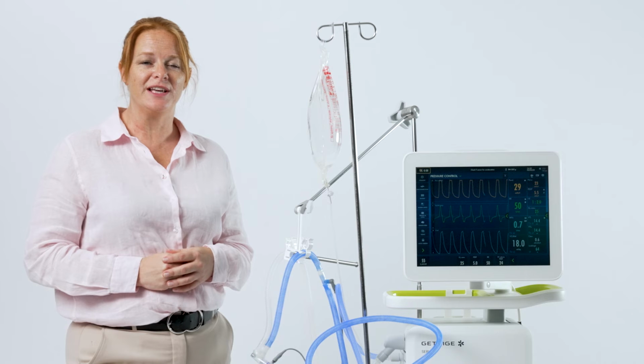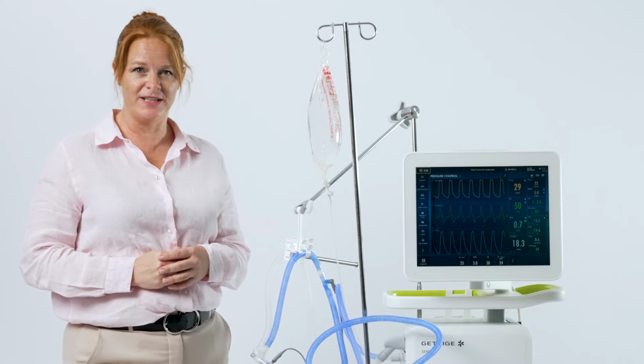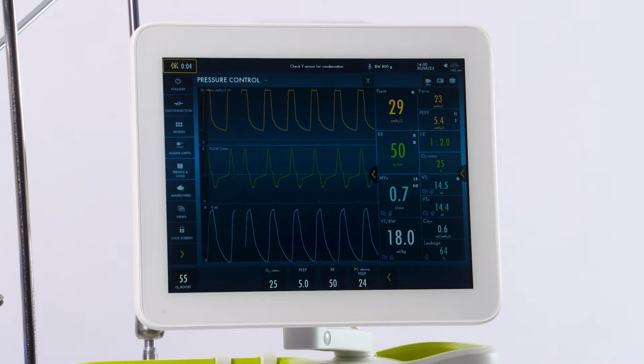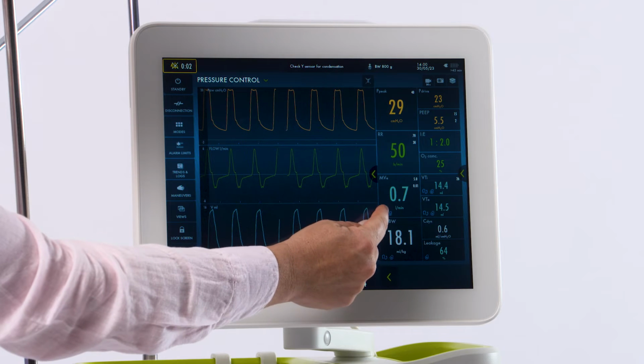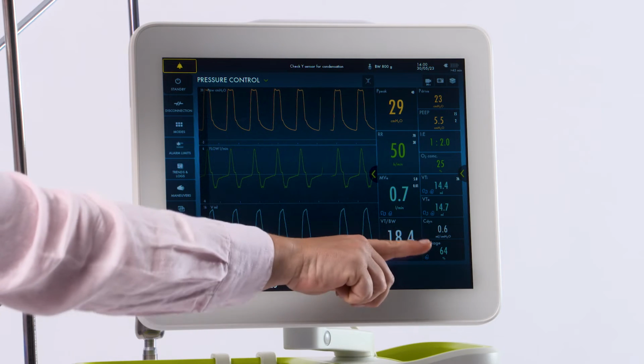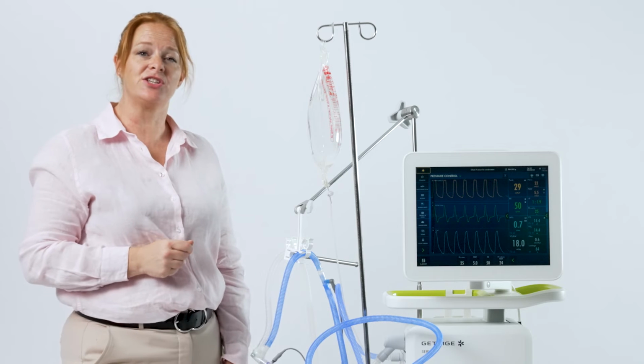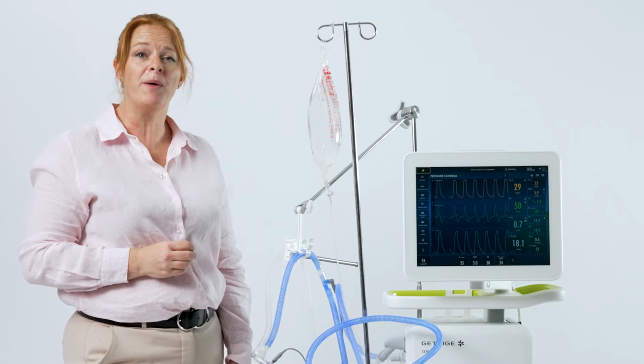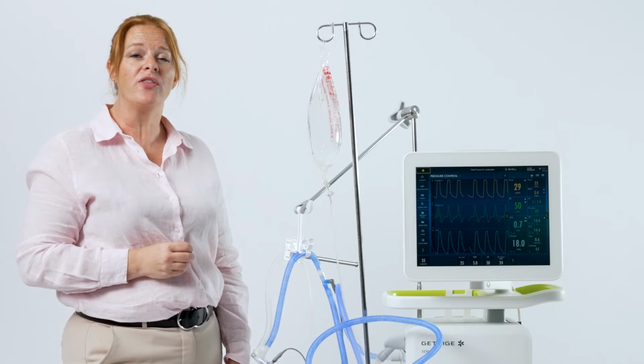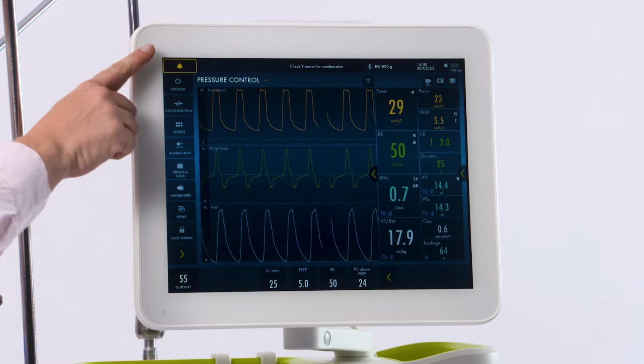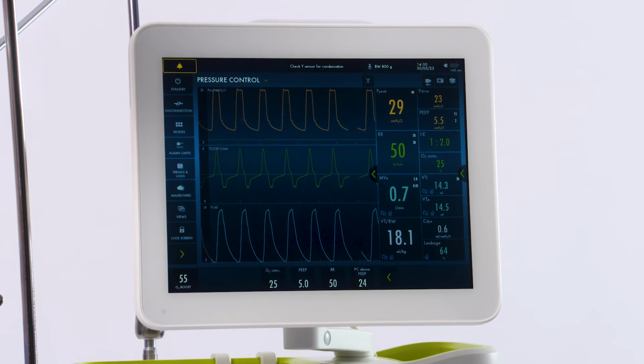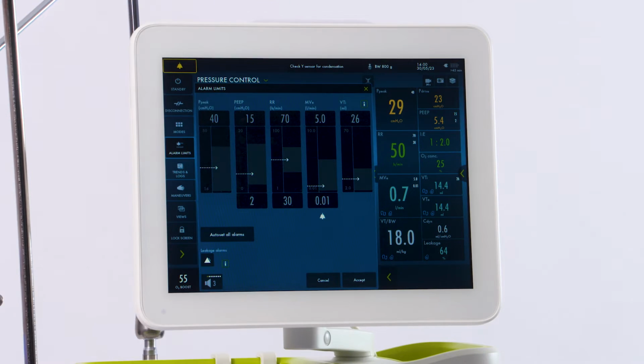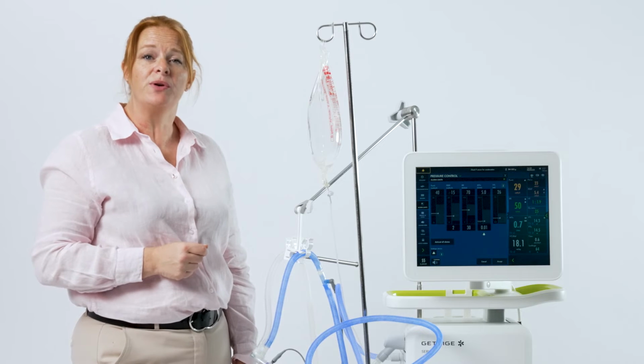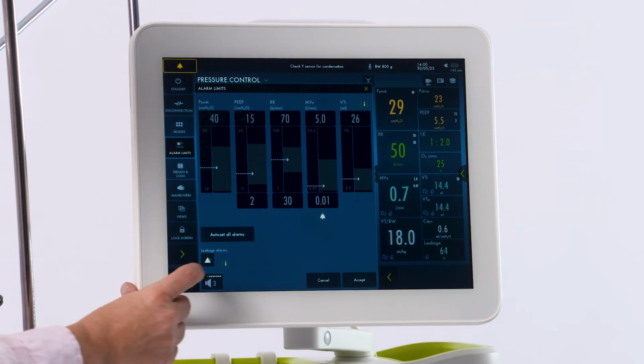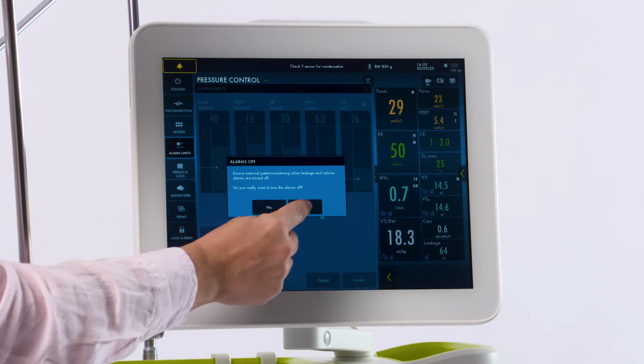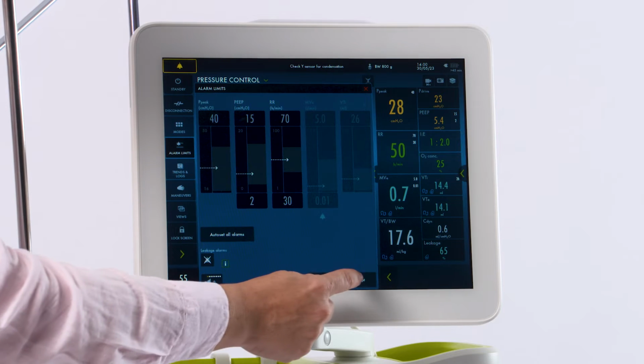Leak compensation is available in neonatal and invasive ventilation on the Servo-n. It's indicated over here with the lock on your volumes. You will also see the leakage calculated at the bottom. Remember, the volumes that you're seeing are the corrected volumes. Also, when you look at your alarms, you will notice at the bottom, it will say leakage alarms. You can turn off the audible for this simply by pressing the audible and hitting yes and accept.